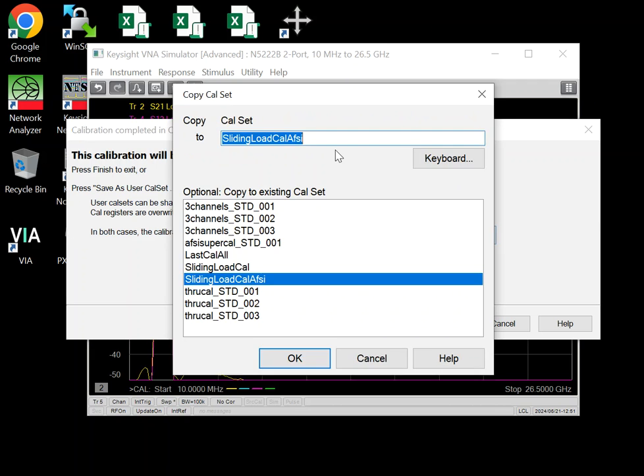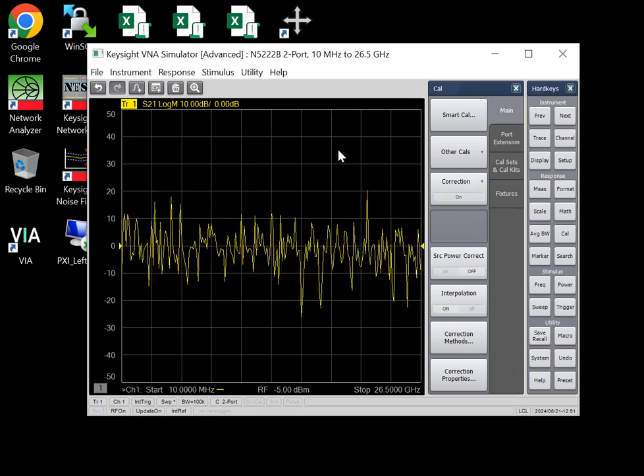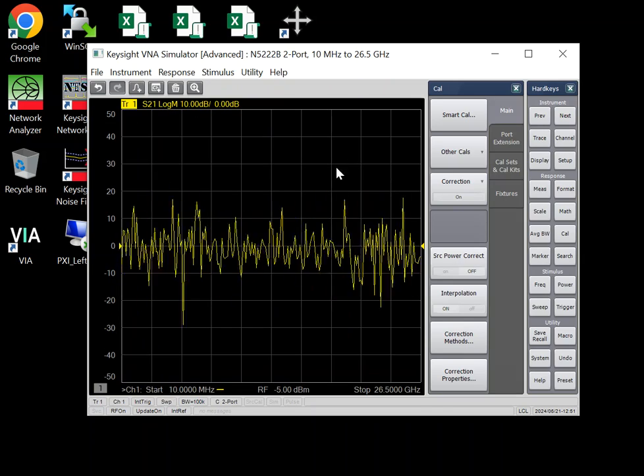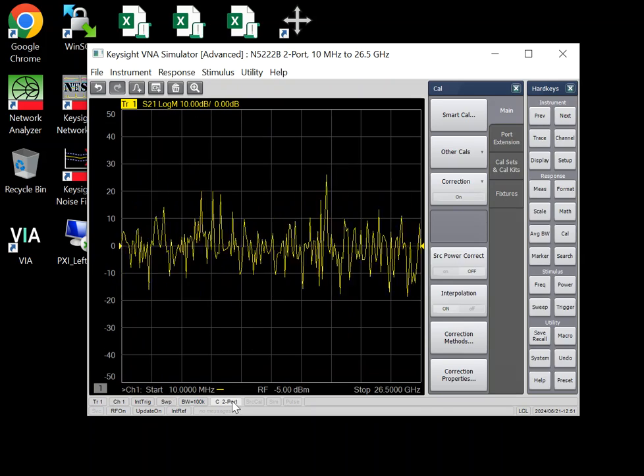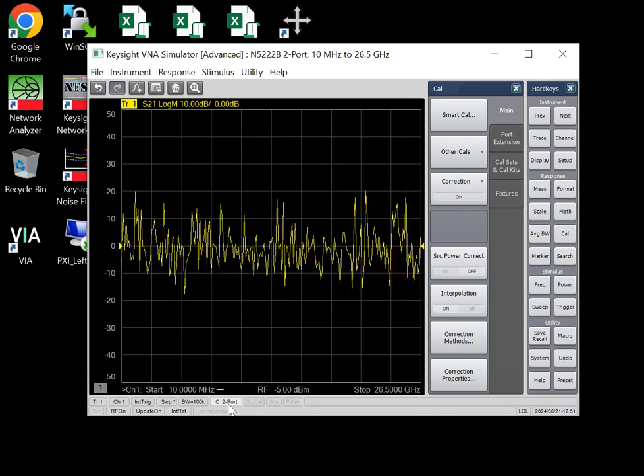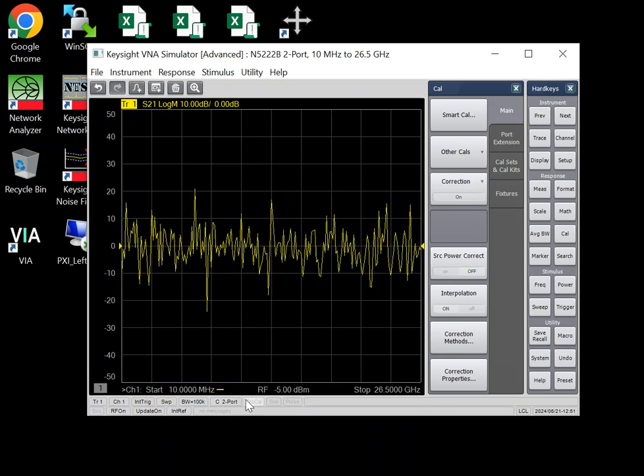And now this is, for example, an 85052D Cal. So these are both two-port Cals, and you can see here it says C two-port.